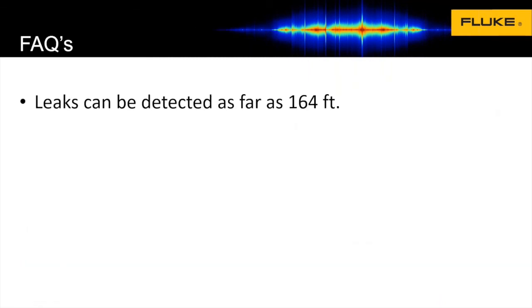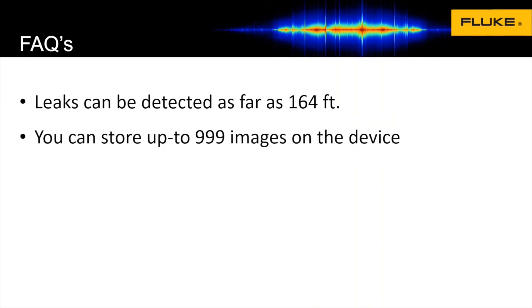Here are some other frequently asked questions. I mentioned earlier how far you could be from a leak and detect it — I said 125 feet. The actual spec is 164 feet when you have direct line of sight. I said 125 feet to be a little more conservative, because in all the experience I've had out in factories and facilities looking for leaks, direct line of sight is not something I commonly have. How many pictures can it store? Up to a thousand images on the device, and you can also export images onto your computer. Battery lasts about six hours — Fluke tends to spec things on the conservative side, worst-case scenario.